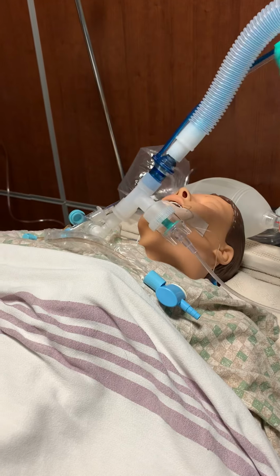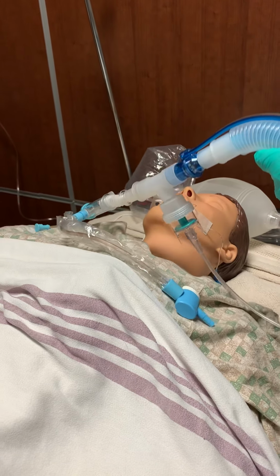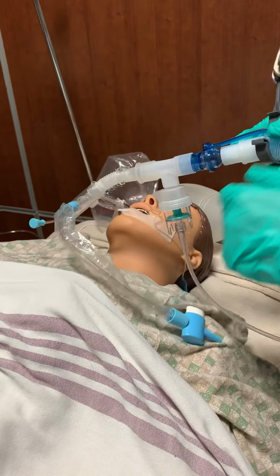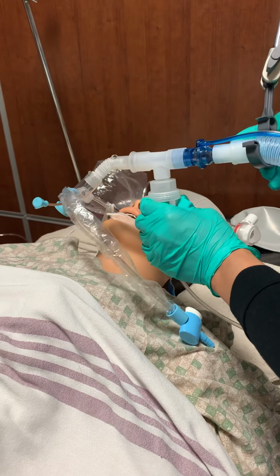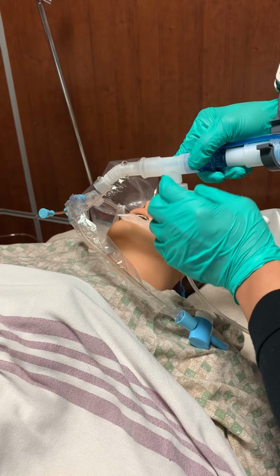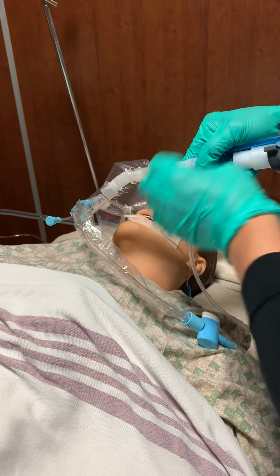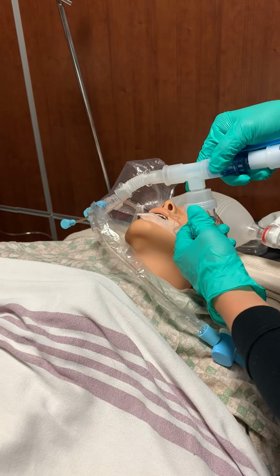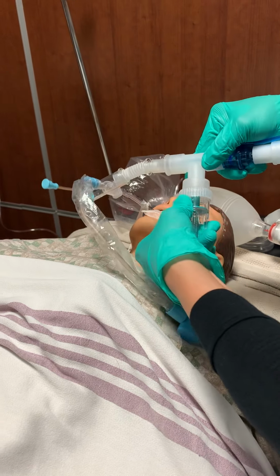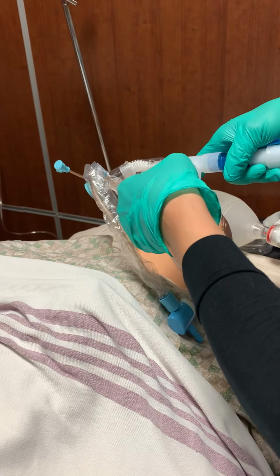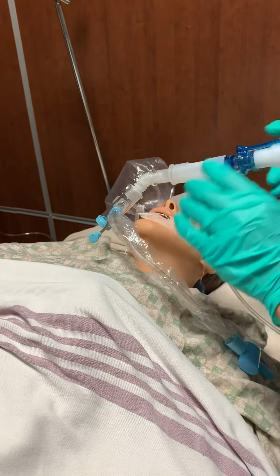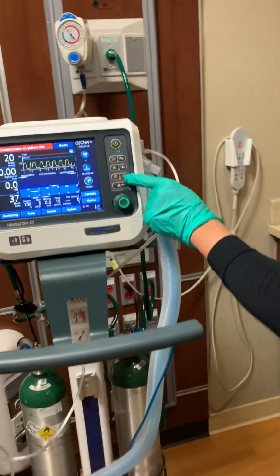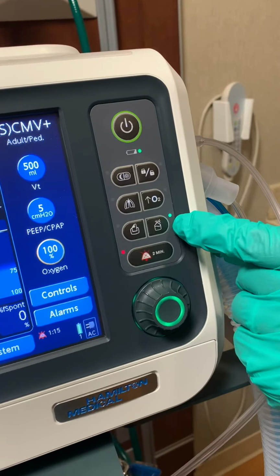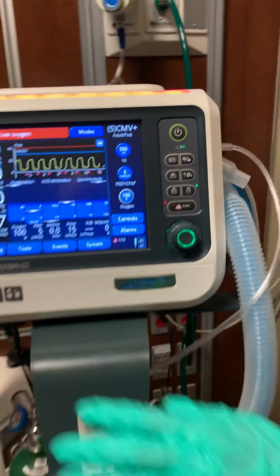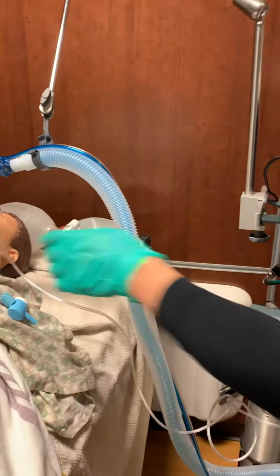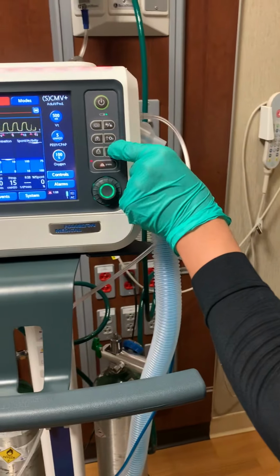We can change it by removing the tubing and then positioning the arm like this. Make sure we position this upright because we want the patient to receive adequate mist from the medication. We should prevent this from being positioned sideways or even downwards. While we give the medication, all we have to do is press this button with the green light, and then we will hear a hissing sound. Once you're all done, you turn this off by pressing it again.